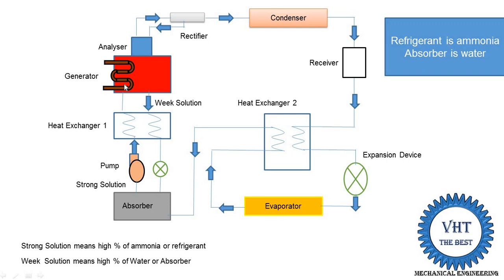When we supply a high-temperature strong solution into the generator, the work done required in the generator is reduced. When the work supplied to the generator is reduced, the COP of the system increases. Heat exchanger 2 sub-cools the refrigerant, increasing the refrigerating effect. Heat exchanger 1 reduces the work done in the generator. The working cycle is now complete, and the system continuously runs based on the circulation of refrigerant and ammonia solution.